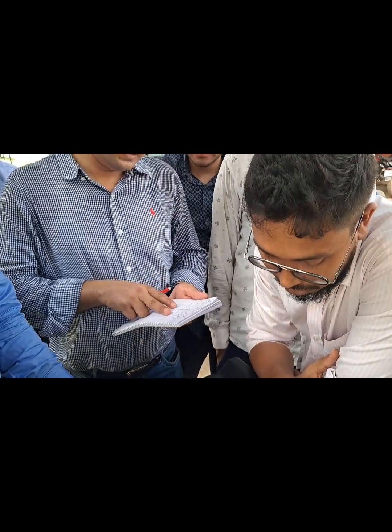Okay, now the ARM is finished. We just have to do HV off, then we can perform the action. Now I can understand that my cable length is approximately 35-36 meters. The fault is at the last distance. You identified that? Then in this case you can directly cut the last end of the cable.